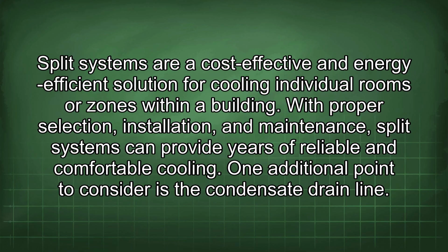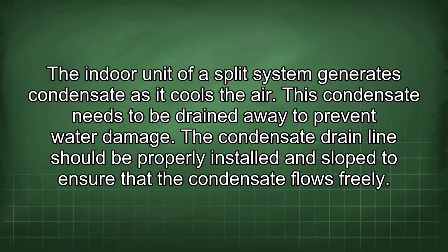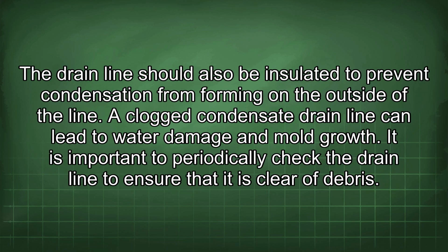One additional point to consider is the condensate drain line. The indoor unit of a split system generates condensate as it cools the air. This condensate needs to be drained away to prevent water damage. The condensate drain line should be properly installed and sloped to ensure that the condensate flows freely. The drain line should also be insulated to prevent condensation from forming on the outside of the line.